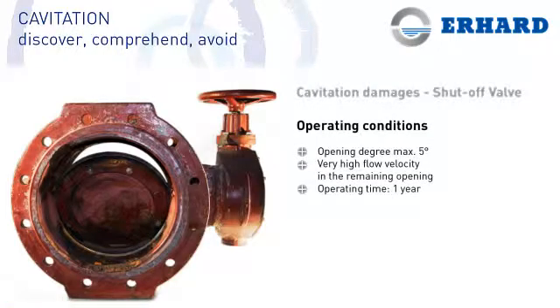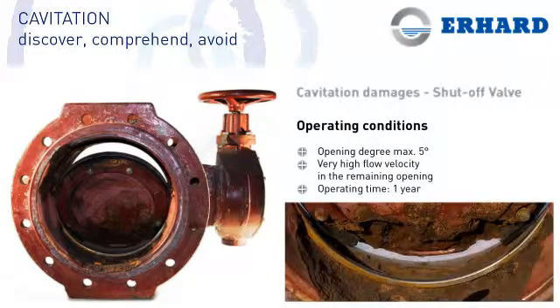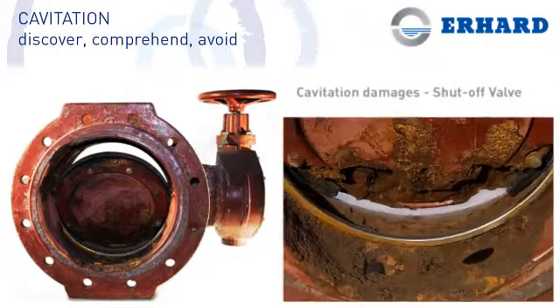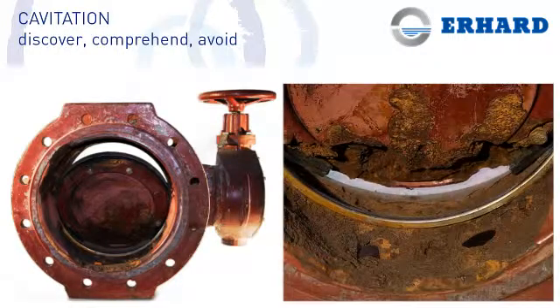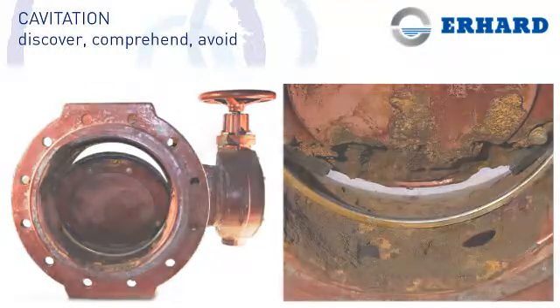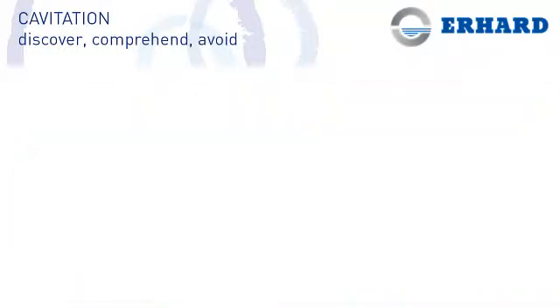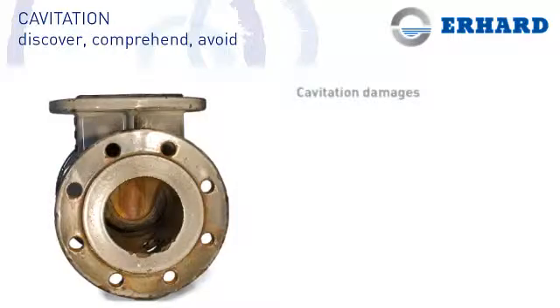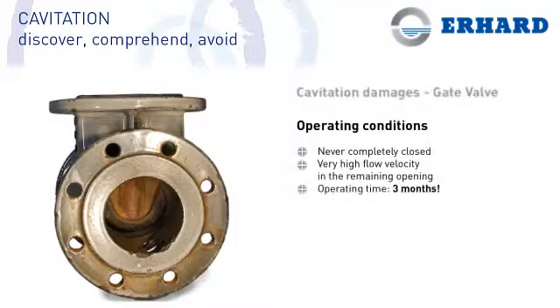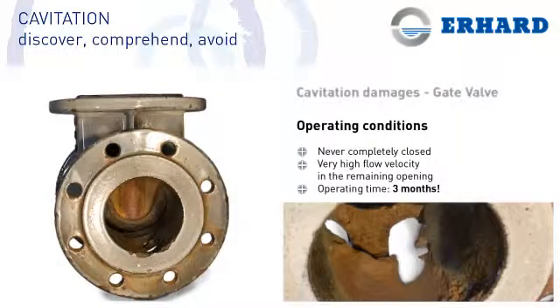Cavitation damage to a shut-off valve used as a control valve — the valve had to be replaced after only a year. This gate valve, which was never completely closed, reached the end of its life after only three months.